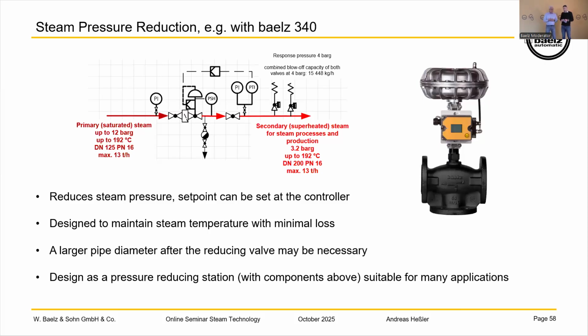For electric actuators it is a little bit different, because then you have to make a spring package on it to close the actuator. Electric actuators normally stay where they are when there is no energy or power. But when you put a spring package on it, you are closing the valve, so it is automatically closed when there is no power, electricity, or compressed air in the actuator. Correct. And when is the valve closing? At over temperature on the secondary side, or over pressure, whatever you are doing in your control system. Or when there is no electricity or compressed air on the valve. Correct. All right. Thanks.